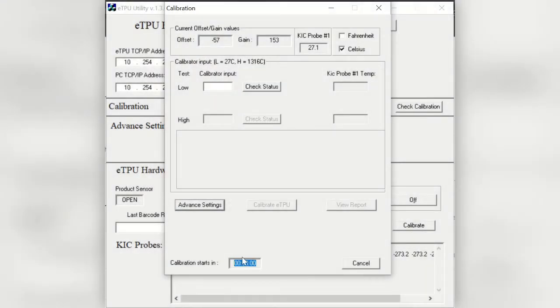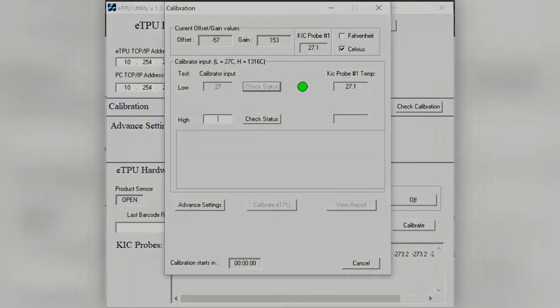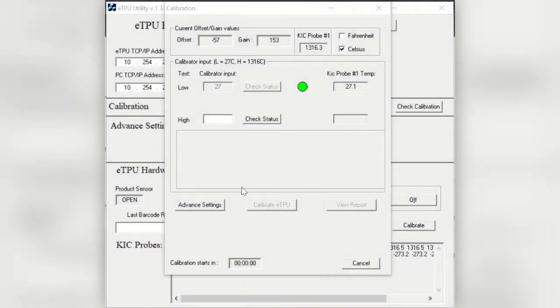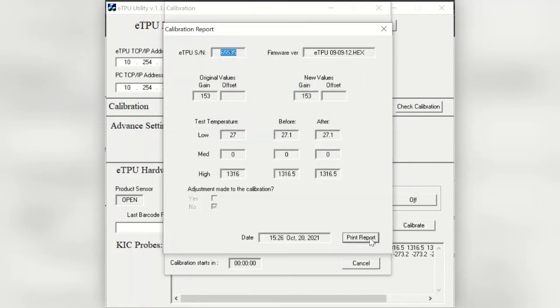Our timer countdown has now reached 0. It means that both the calibrator and the eTPU components should be at room temperature, and we can start our calibration. We set our calibrator to the lower input by writing the same value as in the calibrator into the utility and check the status of the calibration. If it is green, it means that it passed, and we have met the required criteria. We can move on to the higher input and repeat the same process as before. Once our eTPU is inside calibration, we can choose to see the calibration report and save it as a PDF if needed.